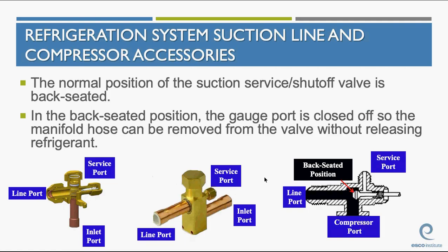We've talked about three-way valves. We've talked about some shutoff valves here, okay? There's a couple different types of it. But a three-way valve, the normal operating position is back-seated. And I showed you this diagram the other day. Normal operating position is back-seated. My service port is here. That's where my gauge hoses go on. Okay, by back-seating, in other words, the stem is all the way out, I'm blocking the service port, but I'm leaving everything else open for refrigerant to flow.